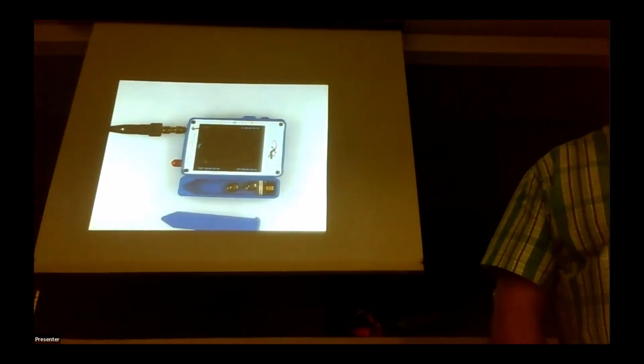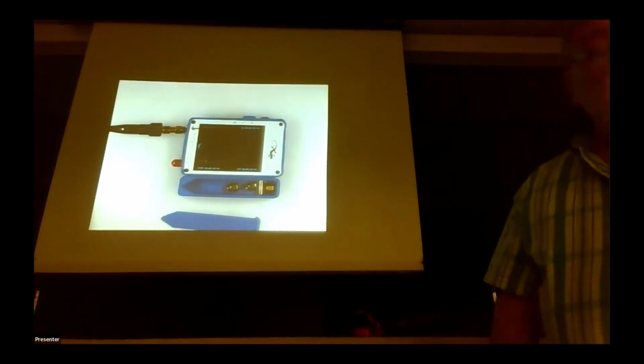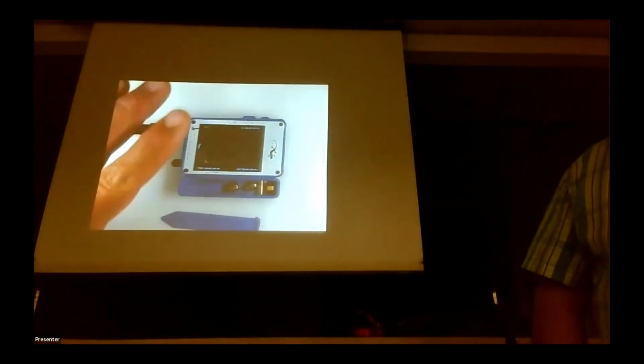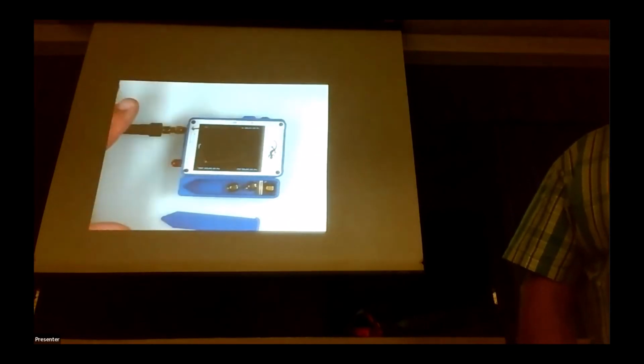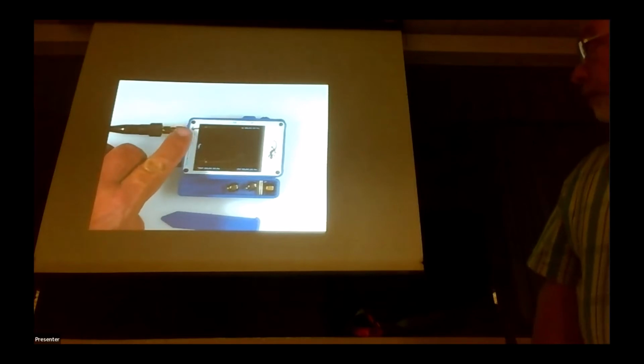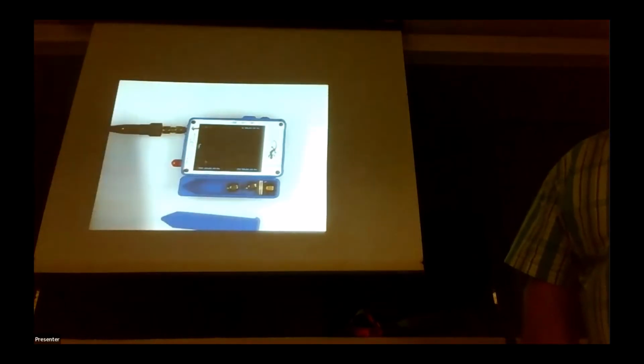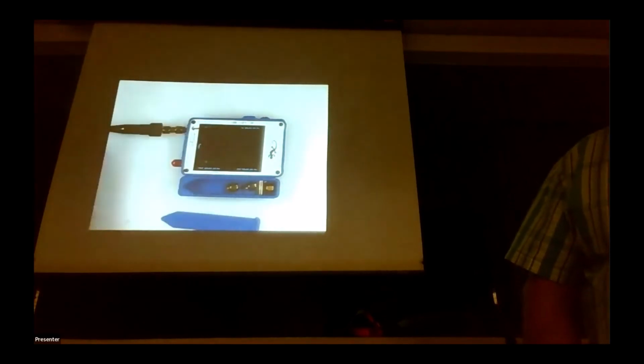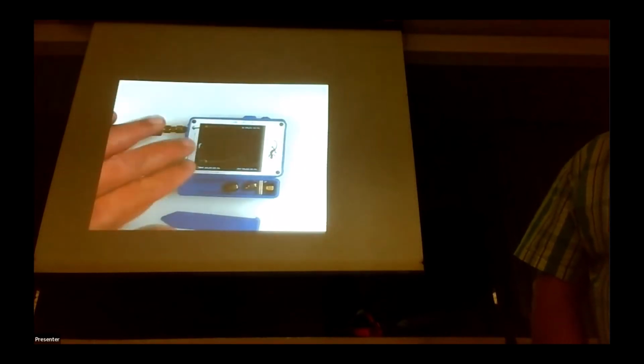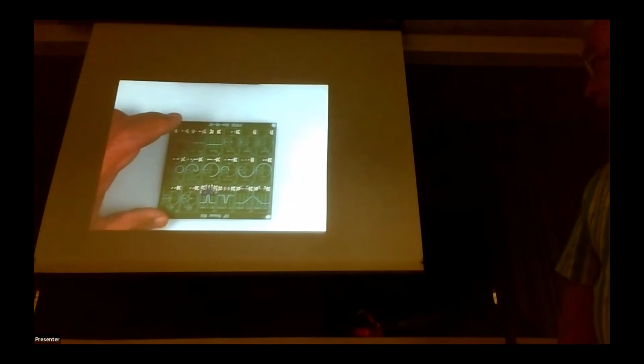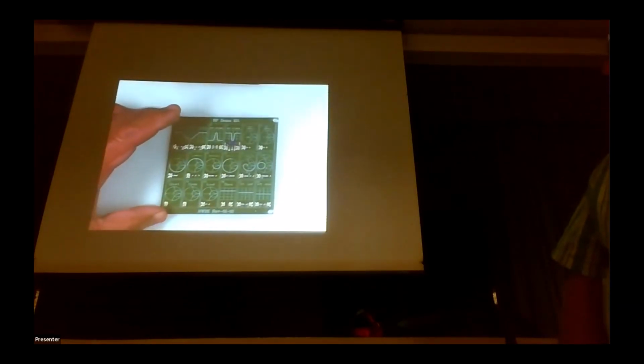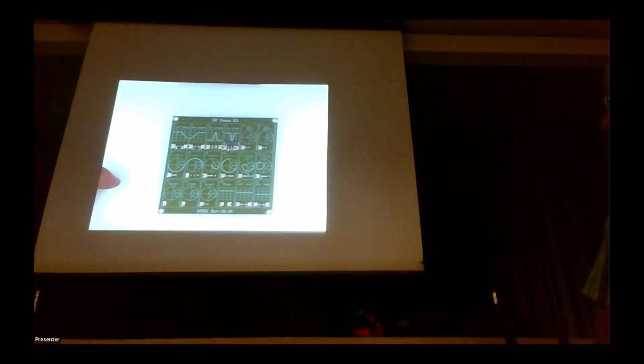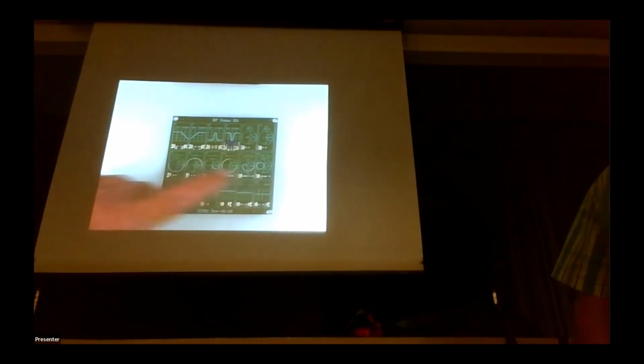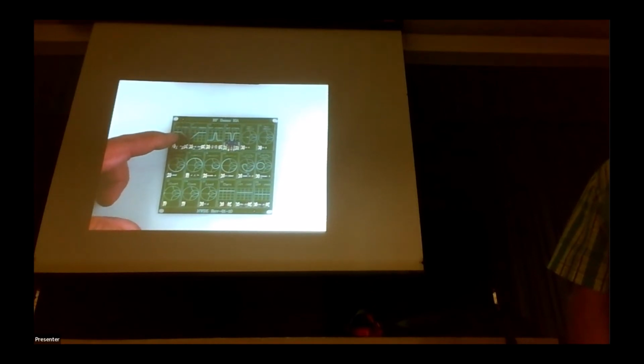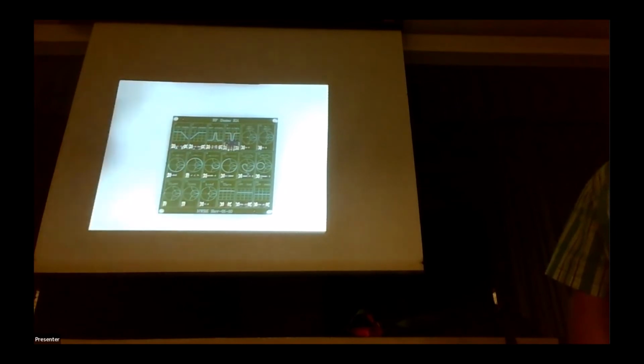This is the SWR, but now I'm going to talk about the calibration. So, okay. So again, not to be a full tutorial on vector network analyzers, on a simpler level, you have two ways to use them. One is a single port, which is what you have here, and it's looking at just the antenna, but you could also use it as a 2-port device where you have an in and an out. And that comes by using a lot more powerful features other than just a simple SWR meter. And one of the things you could do is get this optional calibration board, which has a number of different circuits on it. And you could utilize what they call the Smith chart function, or a simple network analyzer where you can see what filters look like, especially when you have a 2-port.